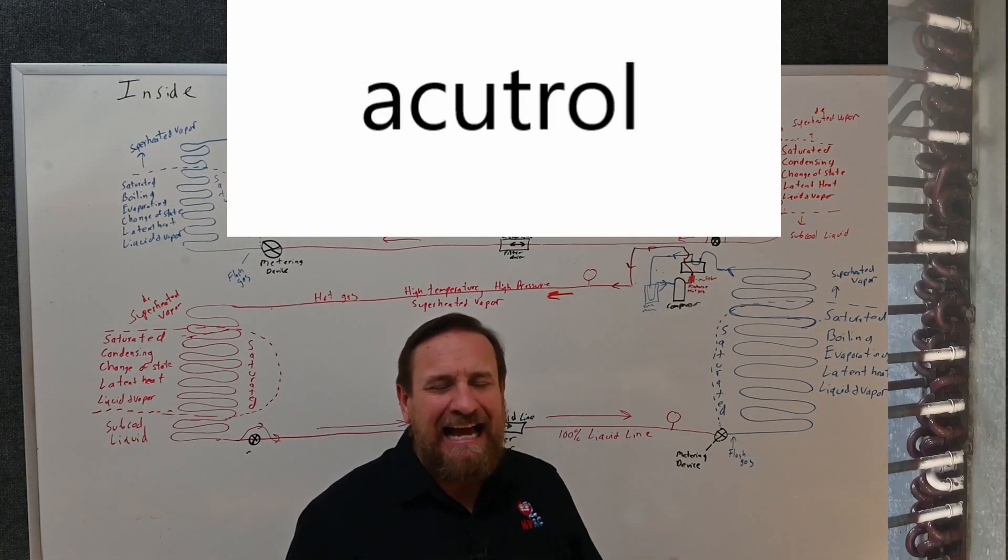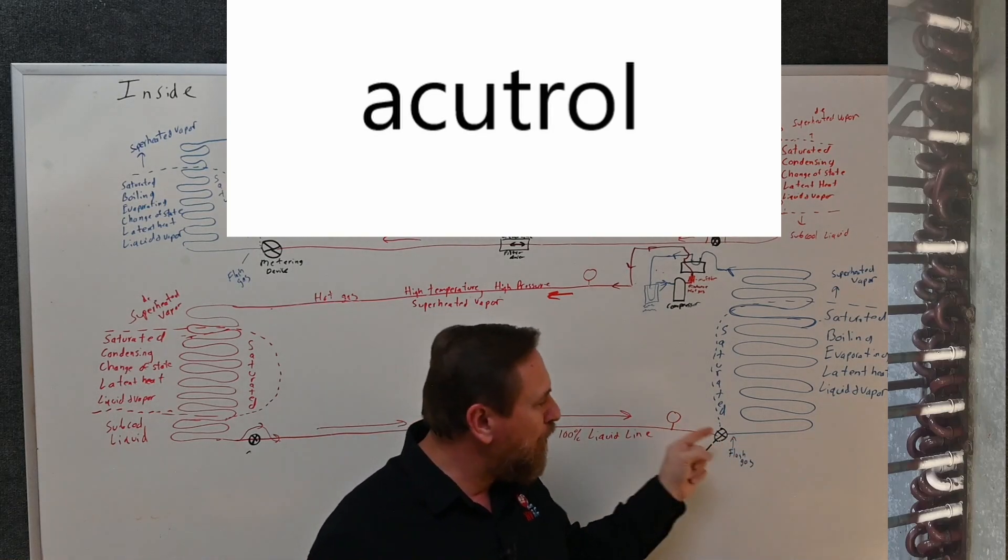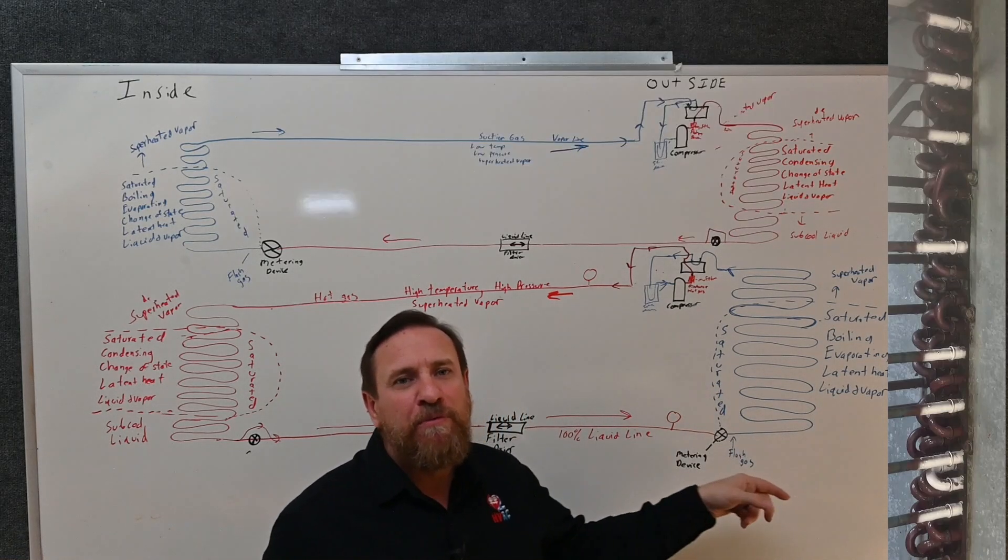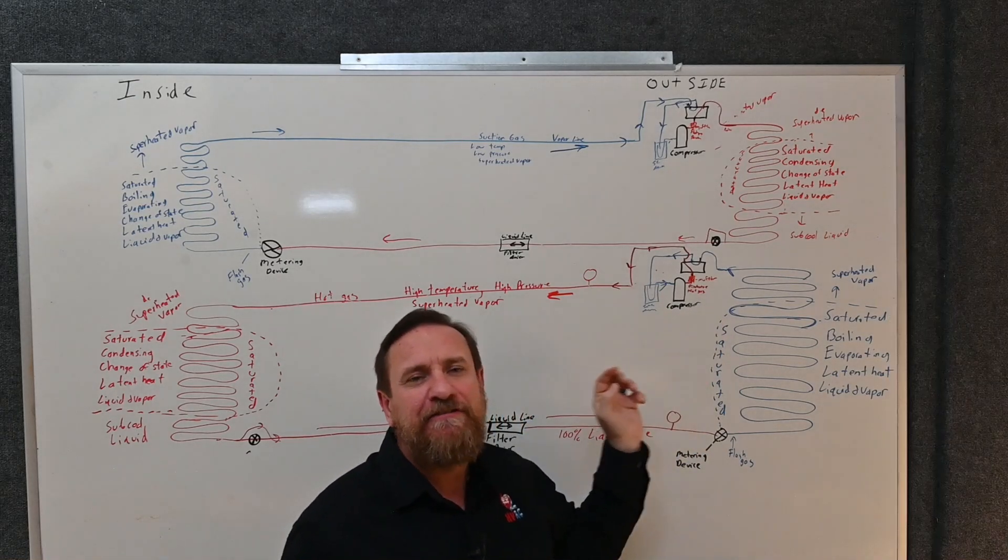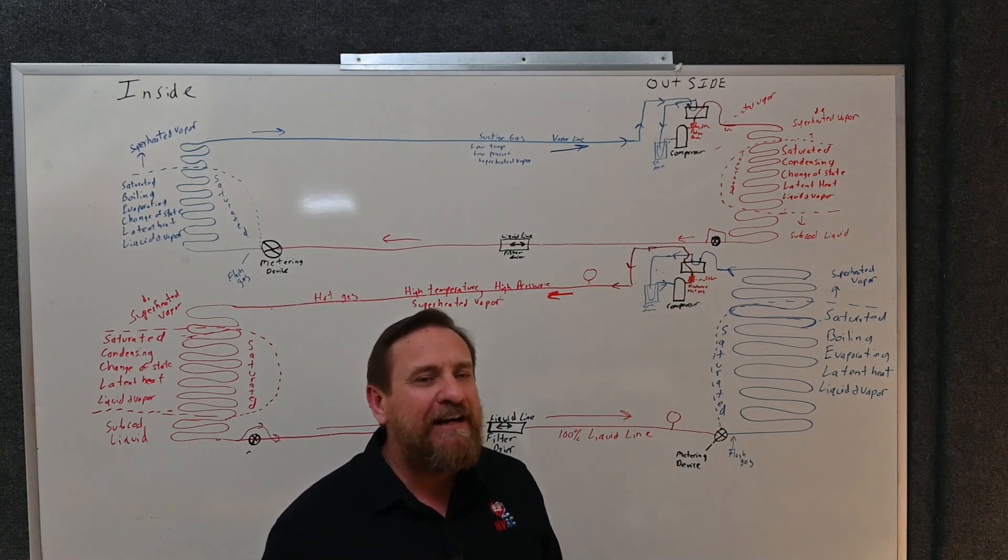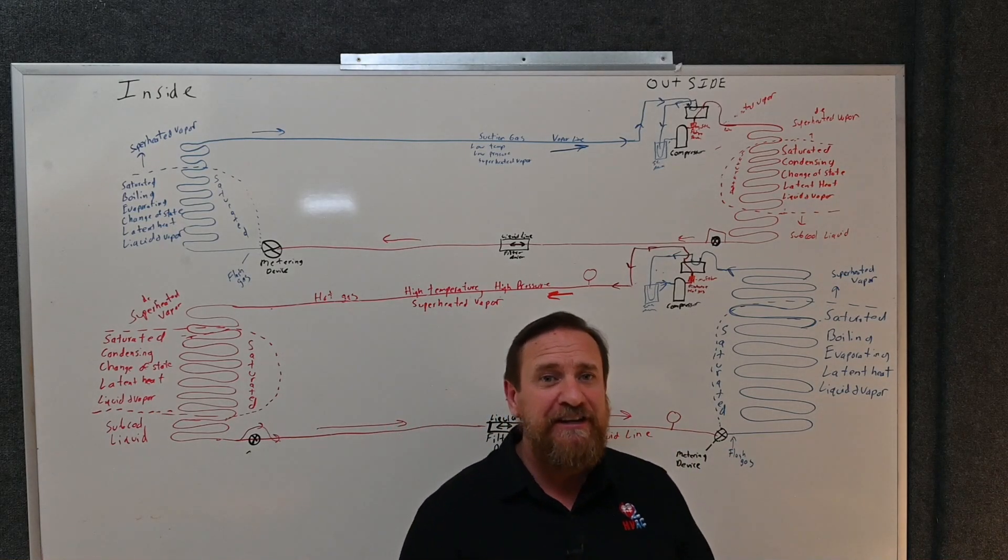Carrier likes to use these Acutrol—I can't remember the name of it—but there's like these little bitty meter devices for their package units. Instead of having one meter device feeding the outdoor coil, we'll have five or six or seven or eight or ten different little bitty meter devices feeding the outdoor coil. Those meter devices, especially the ones at the bottom, can get clogged up, and there's little tricks about how you can fix that, but it's another scenario.